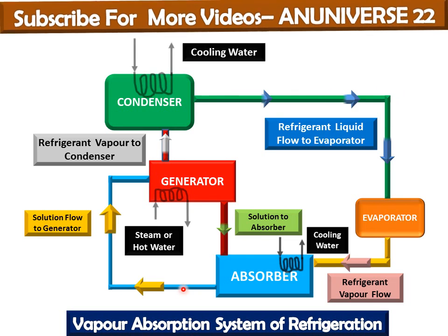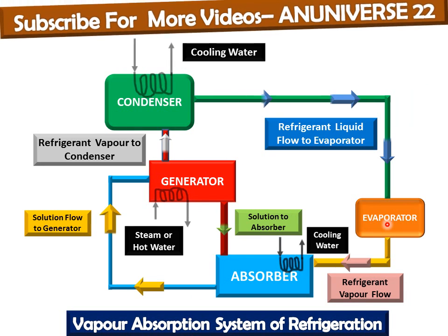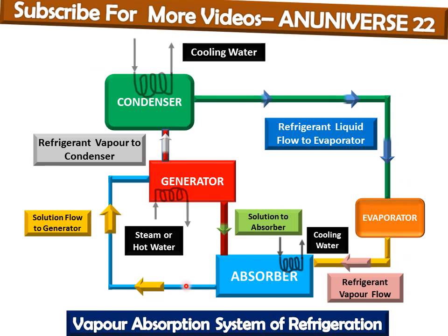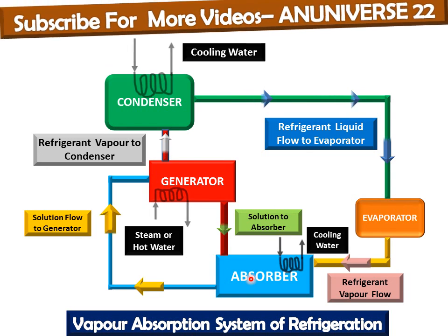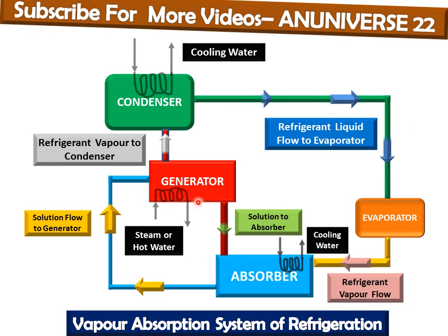So the complete cycle path of the refrigerant — ammonia — is: evaporator, absorber, generator, condenser, and back to evaporator. The path of the absorbent is separate and different; it flows from the absorber to the generator and from the generator back to the absorber.